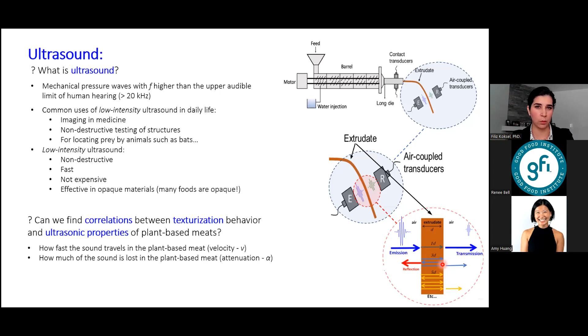But alternatively, the same signal can travel once, be reflected from the interface of the extrudate and air. So this is the interface. So it comes this way and then just leaves on this side. Or it can be reflected once again from this surface, making 3D, so three times the thickness of the extrudate, 1, 2, 3, and then be received by the second transducer. Or it could just keep going 1, 2, 3, 4, 5, and then be received by the second transducer. And it goes like 1 thickness, 3 times the thickness, 5 times the thickness, 7 times the thickness. And I'll come back to these traveling distances, because it's going to be important when we're analyzing our signal.